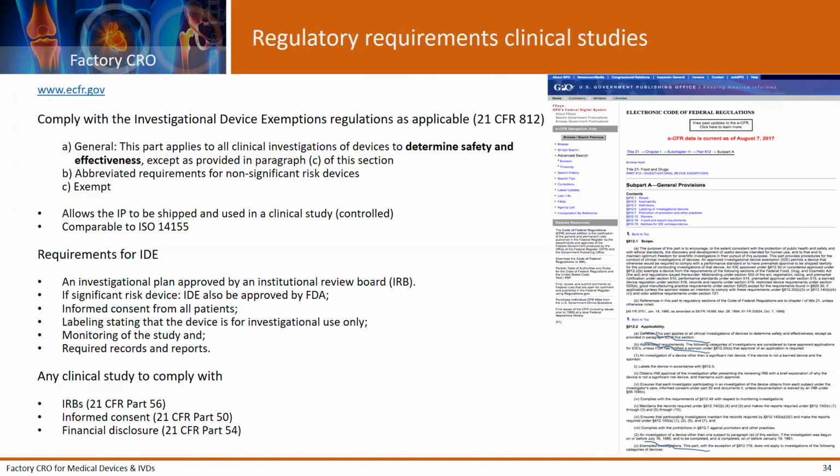The requirements are as follows for an IDE study. You should have an investigational plan approved by the IRB. If it is a significant risk device, your IDE should be approved by the FDA also. You should have voluntarily informed consent from all patients.